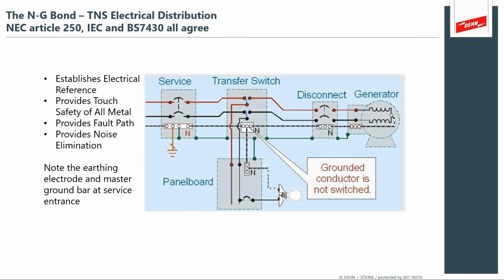Now, what's important about an illustration like this is that you'll see that your neutral is now carried through the system, and the earthing is what's provided for your fault protection. And what's really important is that that neutral ground bond only occurs at one point. And that's what I mentioned about all the standards. They all agree you do not provide multiple neutral ground paths. That would create the opportunity for what's called ground loops, and it would certainly introduce a lot of noise potential.